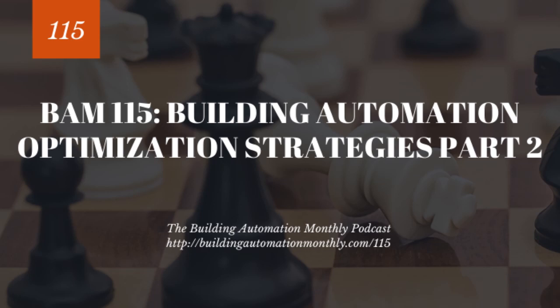So how you approach this, quite simply, is you look at load. But what is load? Now, there's 2 schools of thought on this. One is to look at outdoor air temp. I'm personally not a fan of this because it doesn't take into account the building envelope. It doesn't take into account the solar gain on the building. There's a lot of variables. And plus, a lot of folks don't install the outdoor air temperature sensor in a good location. So depending on that to drive a supply air temperature reset is not the most accurate. It is one way, but it's not the ideal way.